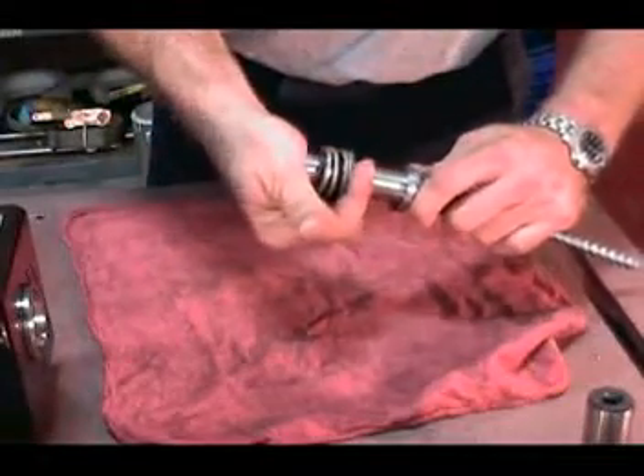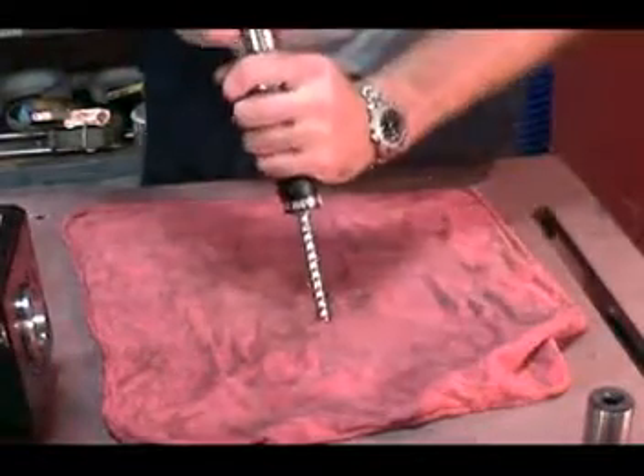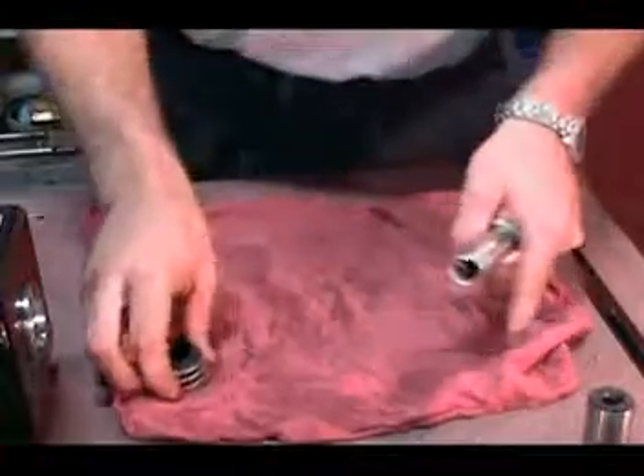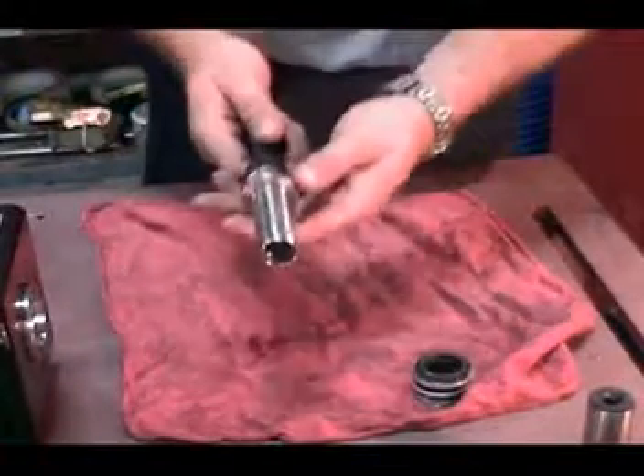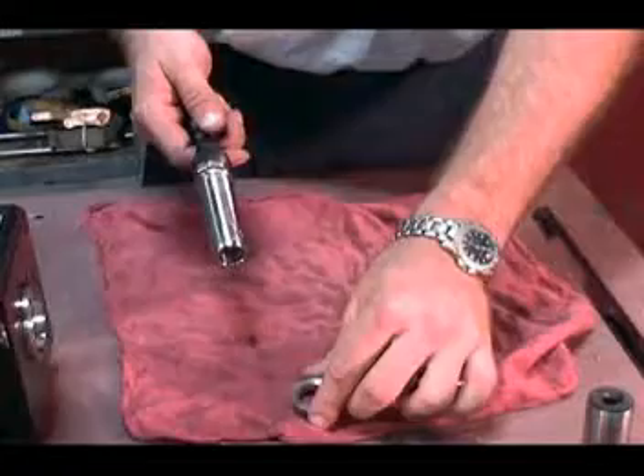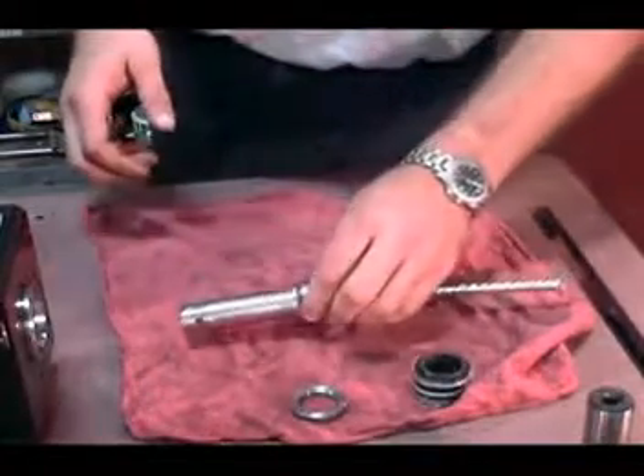Once the plug-in shaft has been removed, you can remove the rotating face of the mechanical seal from the shaft. MD pumps have a spacer ring between the shoulder on the plug-in shaft and the rotating unit on the mechanical seal.